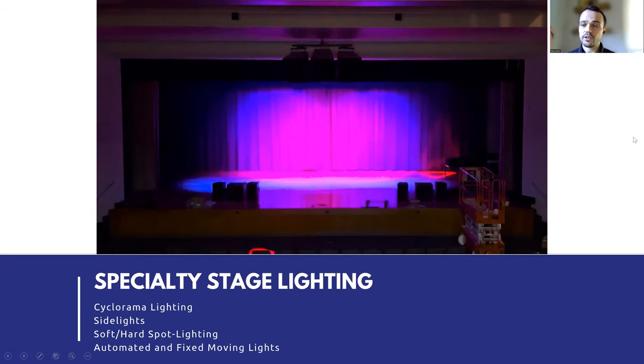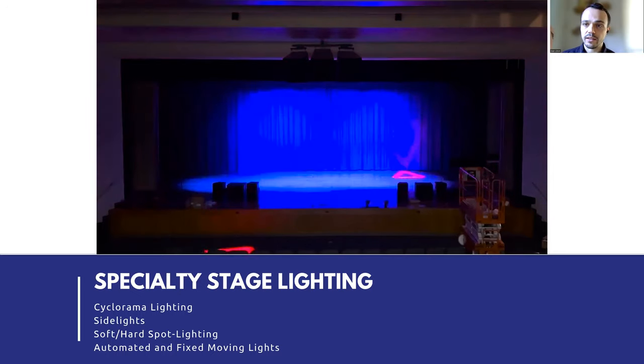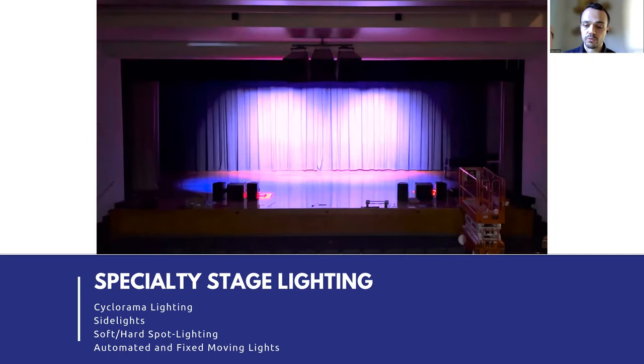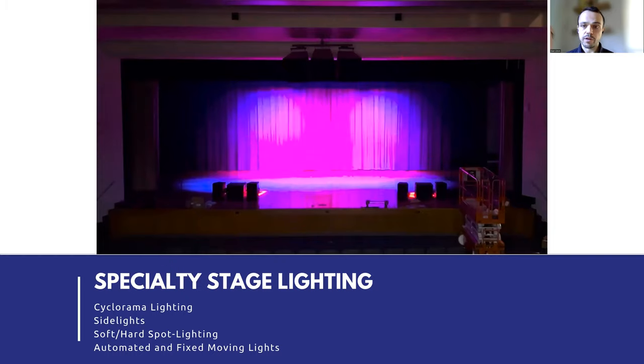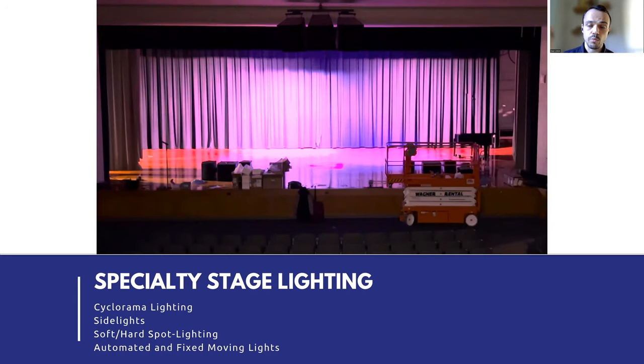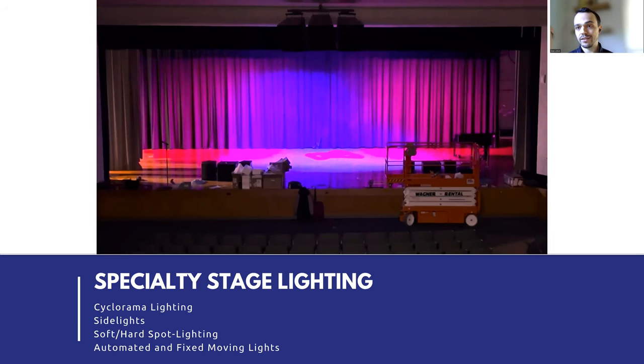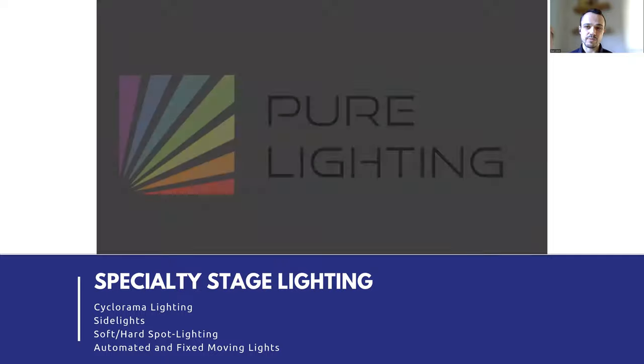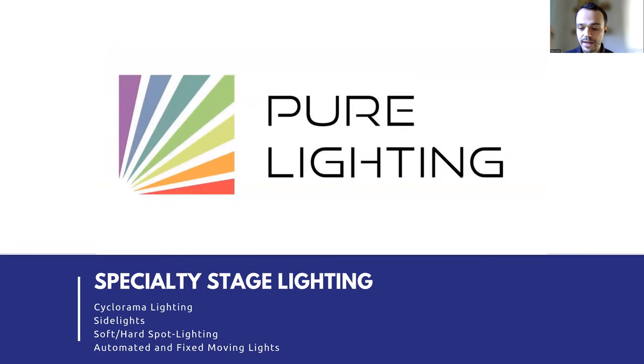Now for this project itself, just a quick aside, this was using wireless DMX, so it didn't require the runs of Cat 5e or Cat 6 cabling from the processor over. In this case, this was done as a retrofit trying to save a little bit of budget. With wireless systems, you do run the risk of crowding in the bandwidth, and when that happens sometimes signal won't work as well as you want it to. You're going to run the risk of latency, so there's going to be a bit of a lag time from when the presets hit to when the action happens. So if there is ability to hardwire, that typically is going to be a more dependable system. But wireless systems are getting better and better, and that's something we'll talk about in our January webinar, the Lighting Controls 101 webinar.